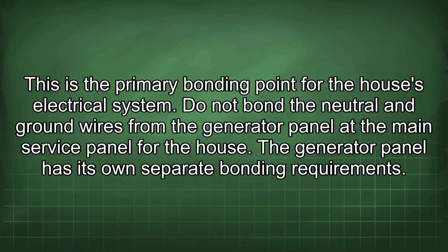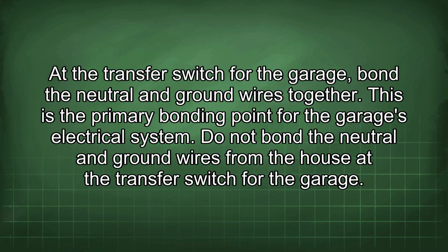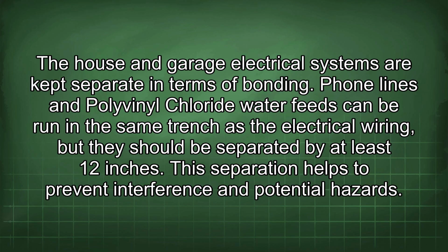Do not bond the neutral and ground wires from the generator panel at the main service panel for the house. The generator panel has its own separate bonding requirements. At the transfer switch for the garage, bond the neutral and ground wires together. This is the primary bonding point for the garage's electrical system. Do not bond the neutral and ground wires from the house at the transfer switch for the garage. The house and garage electrical systems are kept separate in terms of bonding.